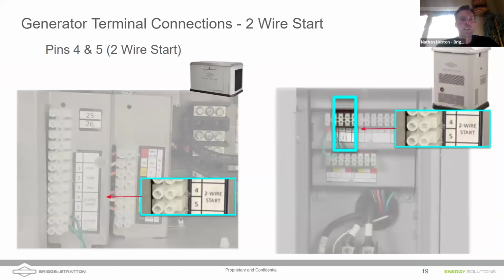I want to point out, Daniel, that although we're showing this with our generator, certainly the Solarc with our batteries will also work with other generators. Obviously, we like you to buy ours, and we feel like they're the best ones on the market. But other generators can be integrated and programmed to start when our batteries get low. So if there's an existing generator on a site, and it's a Kohler unit, don't shy away from the Solarc. As long as it's got that two-wire start, we can still integrate it with our batteries and with our Solarc packages.